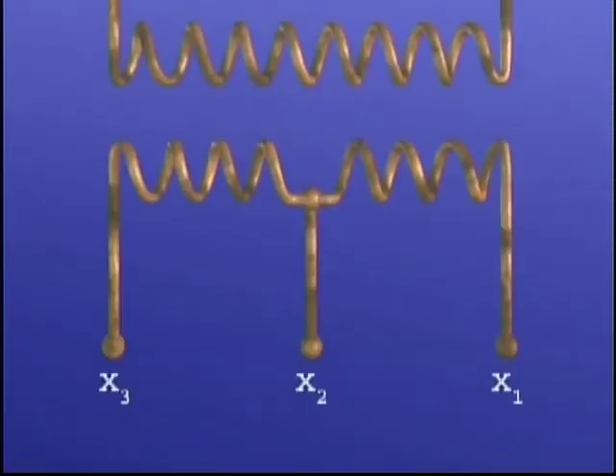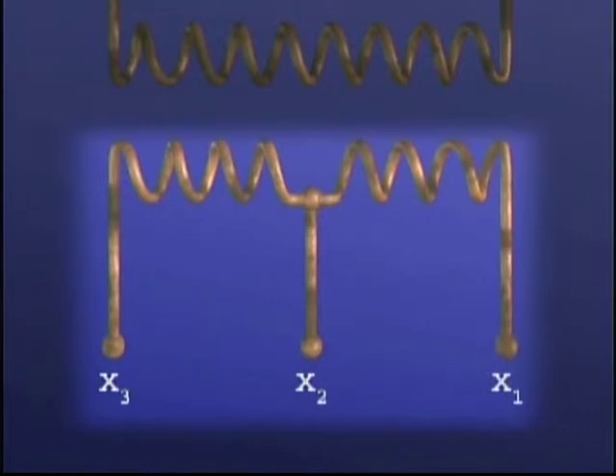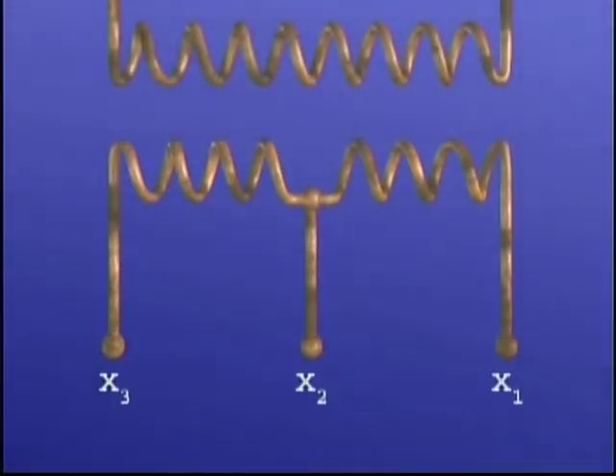There are, however, a couple of things that you need to realize about this example. First, the polarity of the transformer used for our demonstration is additive. This means the secondary bushings are designated as X3, X2, and X1 when read from left to right. If this unit had subtractive polarity, the ends of the windings connected to the X1 and X3 bushings would be swapped internally. The secondary bushings would then be designated X1, X2, and X3 when read from left to right.